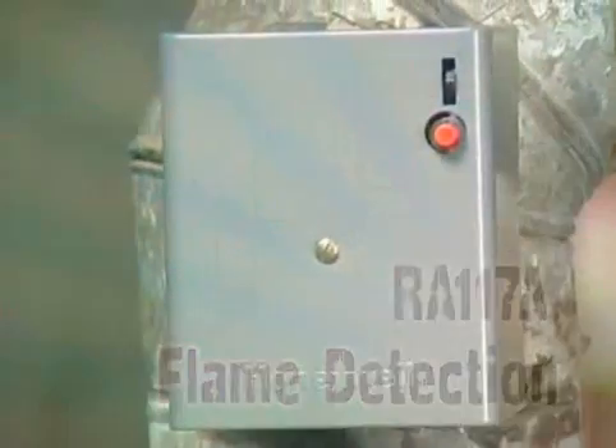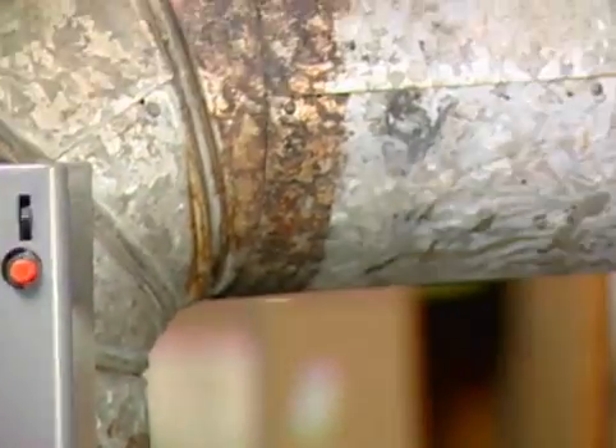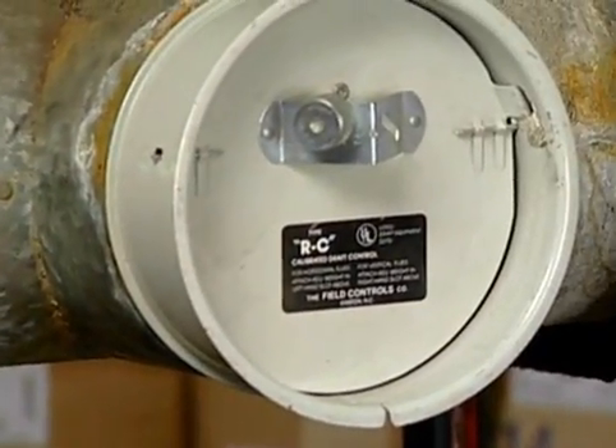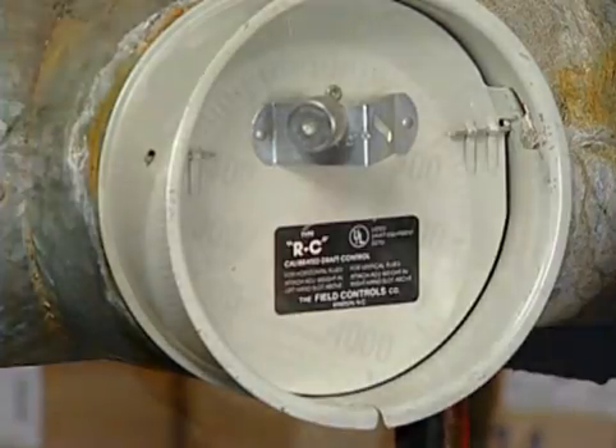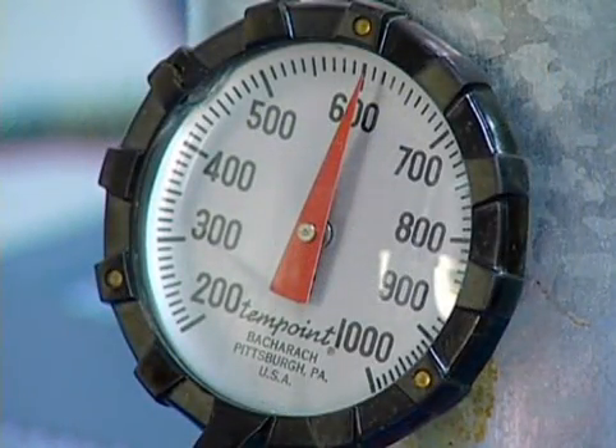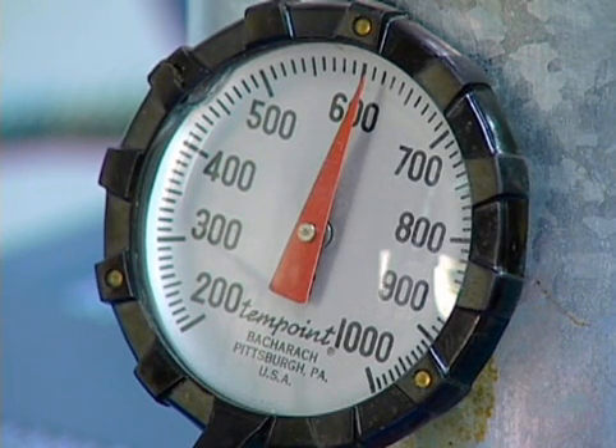The RA 117A employs a bimetal heat-sensing element for flame detection. This heat-sensing element must be in the path of the combustion gases between the heating unit and the draft regulator. It should be centered in the flue pipe at a point where it will be exposed to flue gases between 300 and 1000 degrees Fahrenheit.